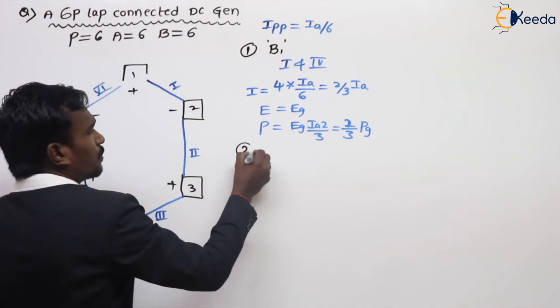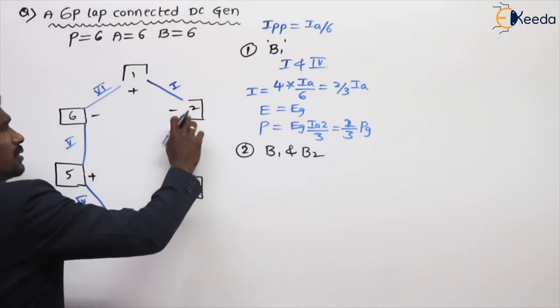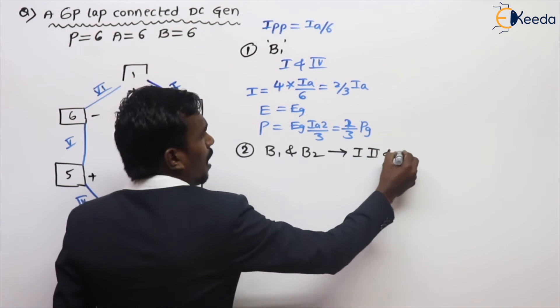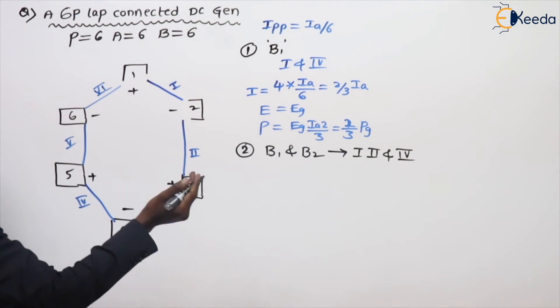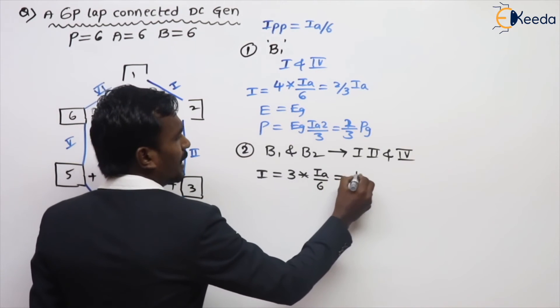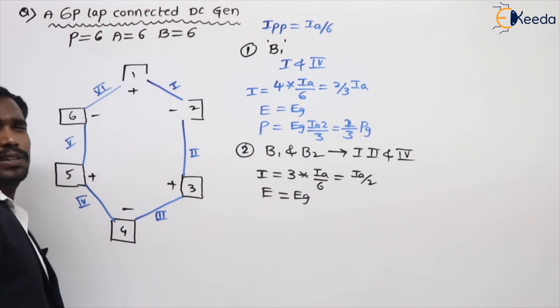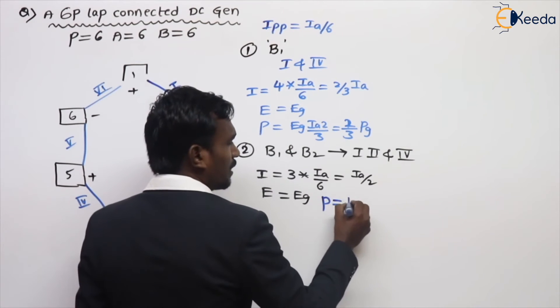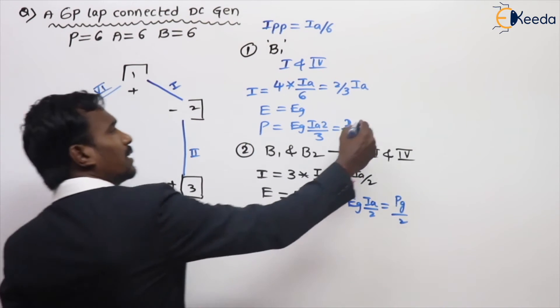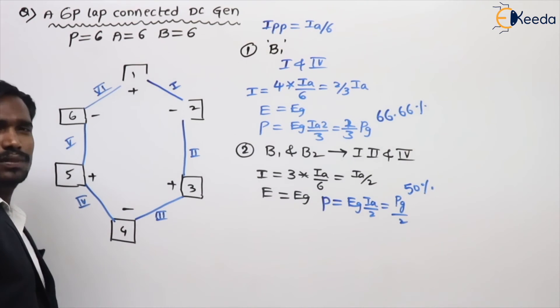Second case for six-pole: brush 1 and brush 2 both damaged. When brush 2 is also damaged, parallel paths 1, 2, and 4 are disconnected — meaning 3 parallel paths are open. Remaining we have only 3 active parallel paths, each carrying Ia by 6. So the current is 3 times Ia by 6, which equals Ia by 2. The EMF is unchanged. Power equals EG times Ia by 2, which is PG by 2 — 50% of power develops.